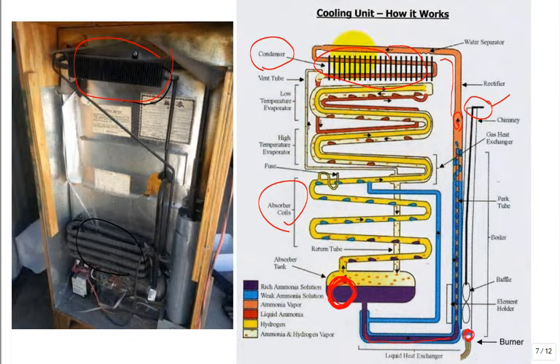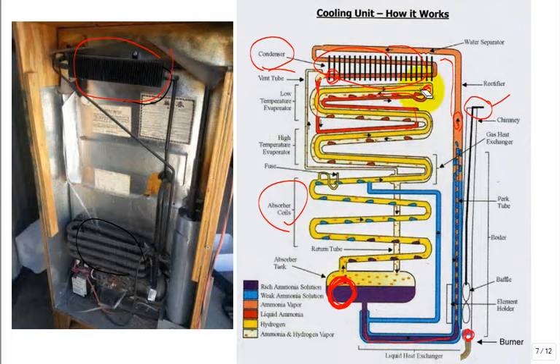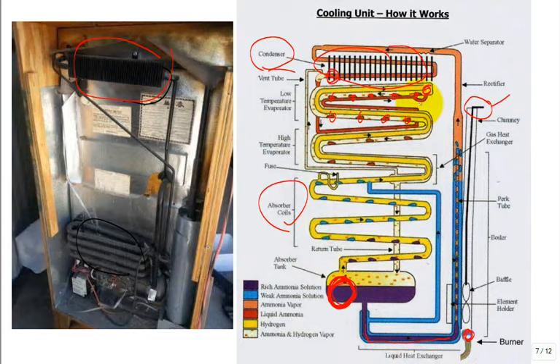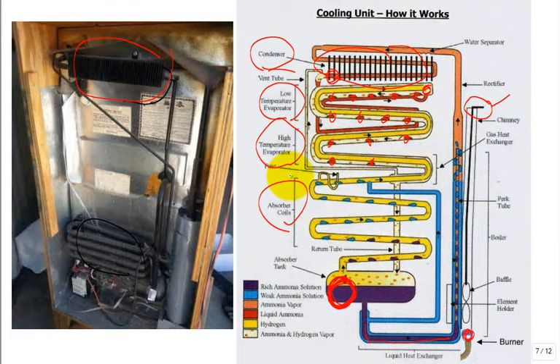It percolates, comes back down on the side, gives up the ammonia vapor. The ammonia vapor comes up, starts to condense. It's liquid ammonia, but you add in hydrogen here. They would like to cool the liquid ammonia, so pass it through the evaporator so it really gets nice and cold. Then let it go into the presence of the hydrogen. You can see the droplets of ammonia evaporating. One, two, three, four, five droplets evaporating. You're evaporating the ammonia as it dribbles through and the hydrogen sweeps over it. You could have a low temperature evaporator and a high temperature evaporator—basically a freezer and a refrigerator compartment.